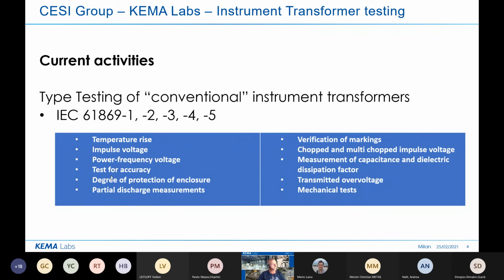And of course, a very important one here is the test for accuracy. And the other tests are a lot of influence testing, isolation type of testing we do on this kind of products. And test for accuracy then also includes, of course, the accuracy from high voltage, high current. But when it comes to current transformers, we also speak about the transient error and the combined error, composite error for instrument transformers for current.